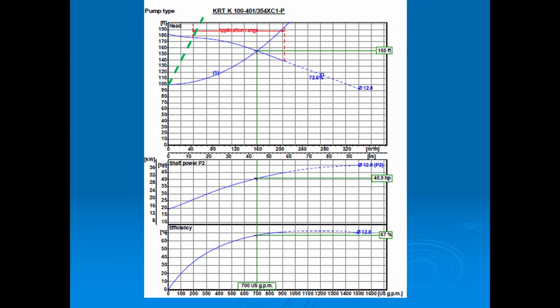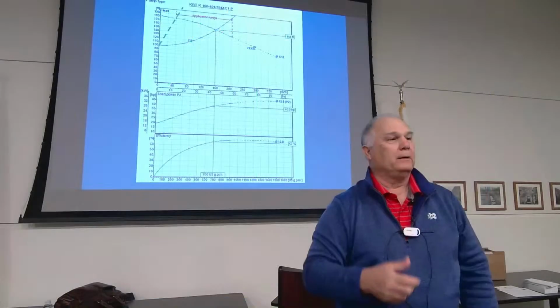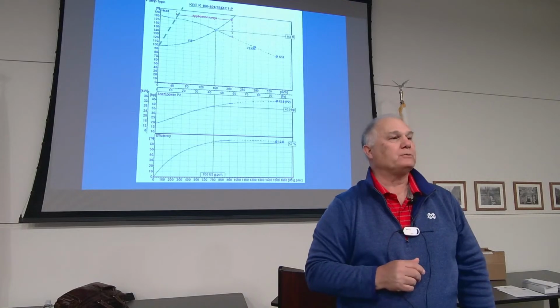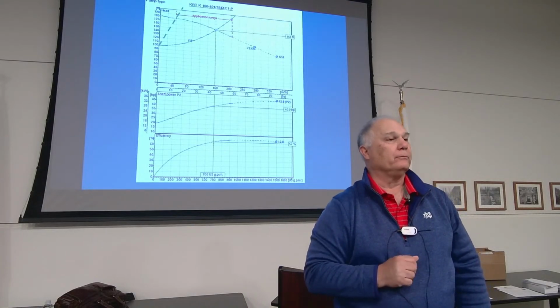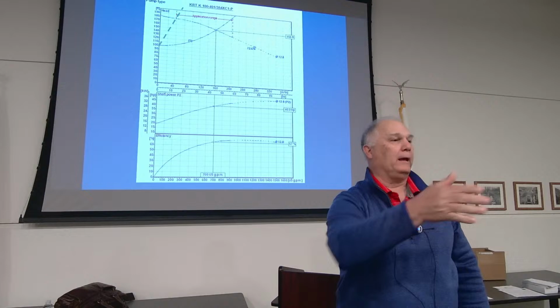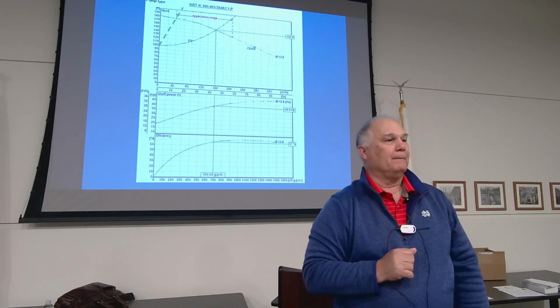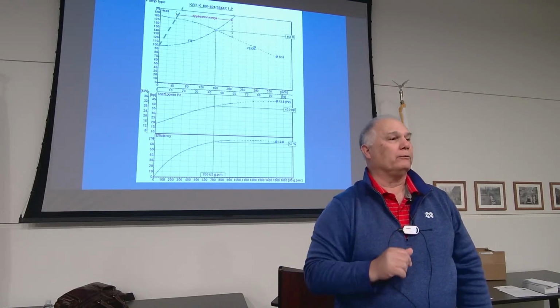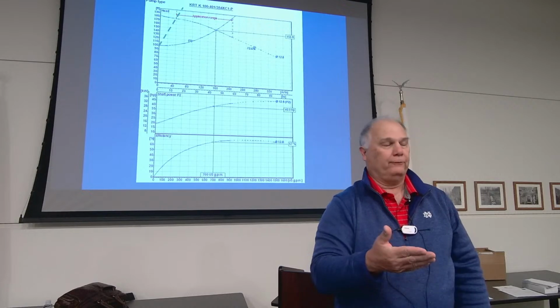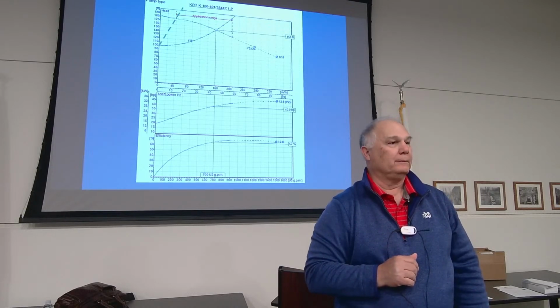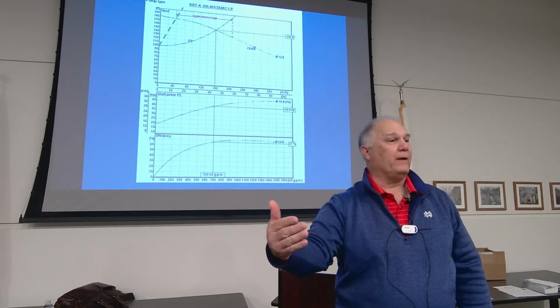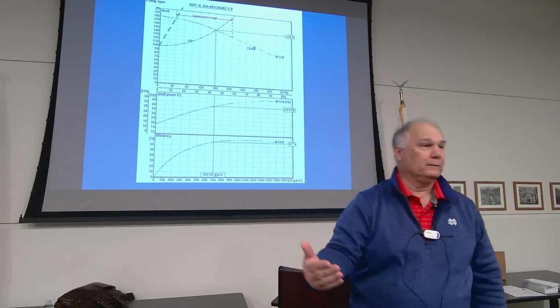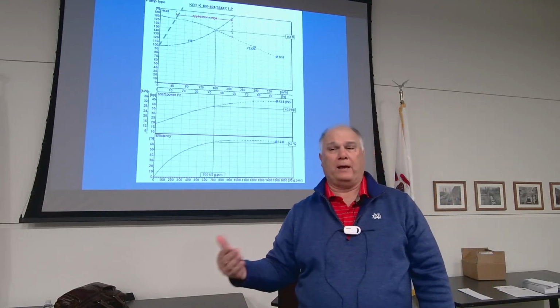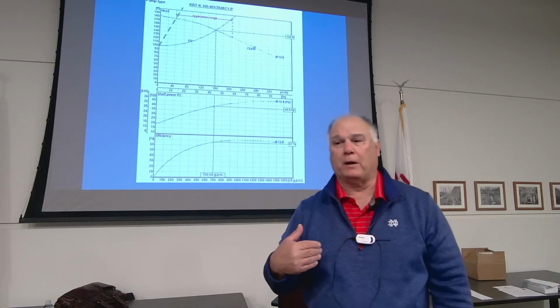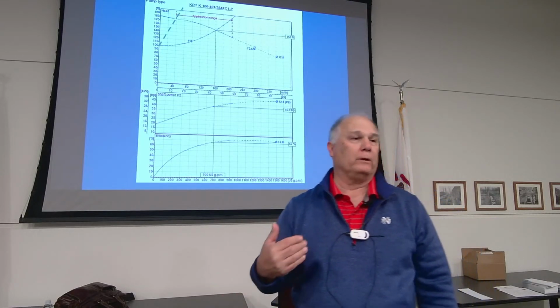So how many people have an amp probe? You go out there with an amp probe, stick it on the pump, and look at the full load amps on the motor, and you're operating at 20 amps. But full load on the motor is only 15. You're operating up in that safety factor. That's never a good thing. Some engineers design it where you can operate in safety factors. We never supply stuff in safety factors. I never want to do that.